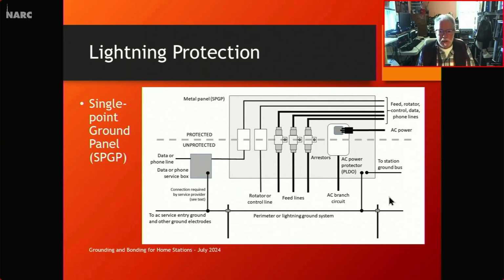So if you create this perimeter system where all of the earth electrodes, these ground rods, are connected together, that's called a perimeter ground. Everything should be bonded to that. And the closer they are together, the lower the inductance is between all the different systems. So here's your protected lines right here, and these are unprotected.